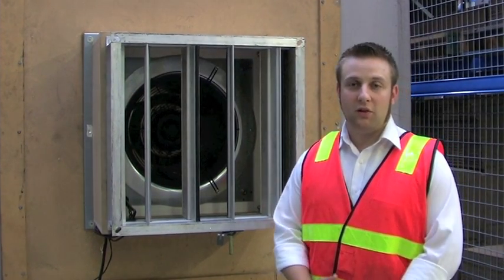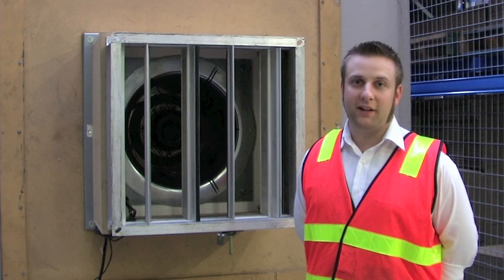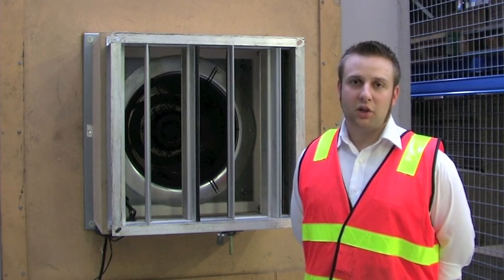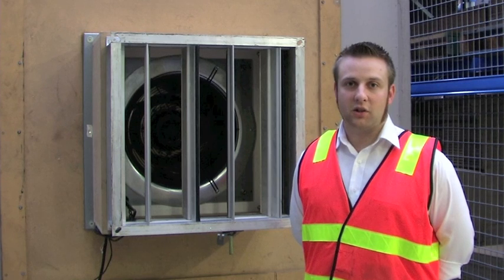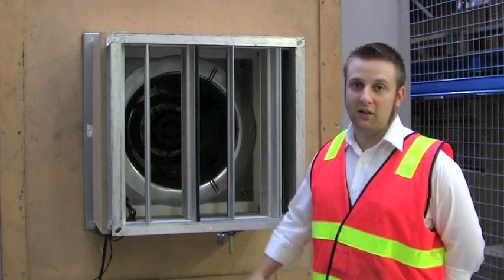Please note we're using one of our EC plug fans with potentiometer speed control as a supply air fan. To determine the airflow at the set static pressure we measure the pressure differential across the nozzle bank located inside the test rig.